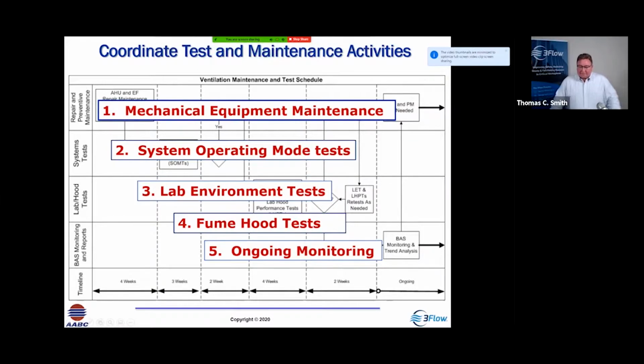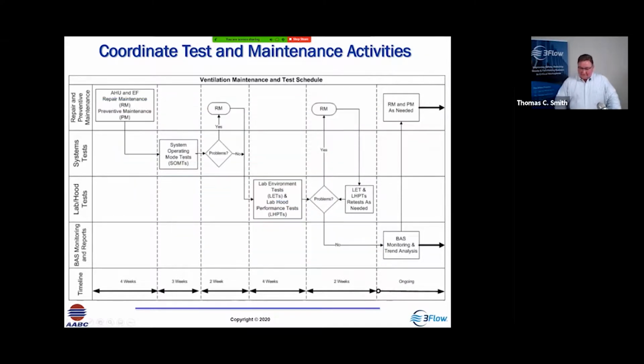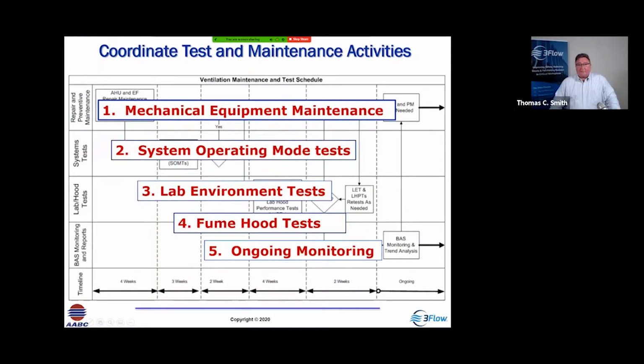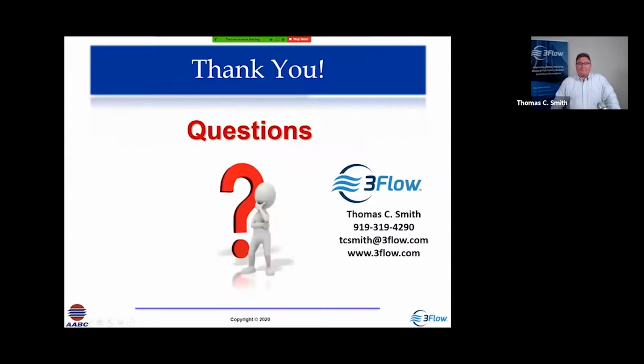Moving from a top-down approach, we go from mechanical systems. Let me go back one. So if we know that the air handler exhaust fans are working properly, we can do a system operating mode test to challenge the systems, then follow it up with lab and then hood tests. And once we do this, we will save a lot of time and effort in optimizing the operation of the systems. So by doing this process, we can not only ensure energy savings, but we can reduce the operational costs, the cost to manage and maintain the systems by an additional 30%, just by changing the order of events. Why test a fume hood before you know the maintenance has been done on the fans? Just doesn't make sense. So this is a better ordering of events.